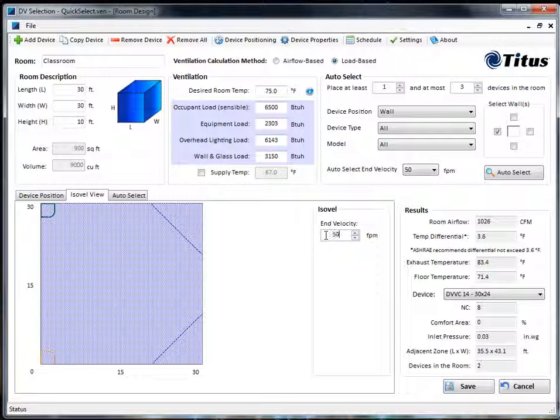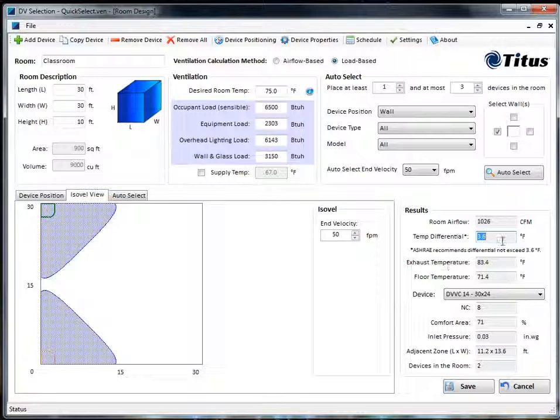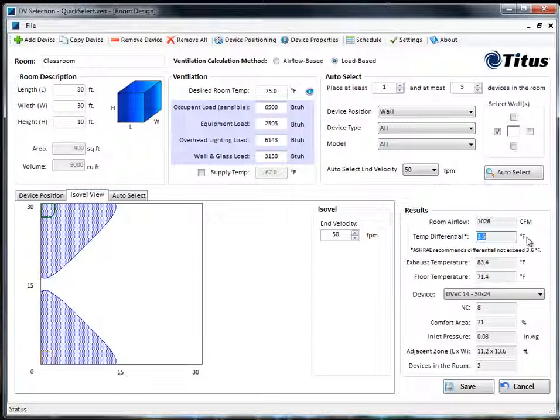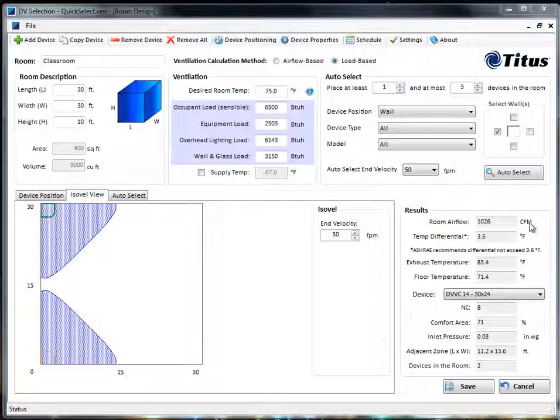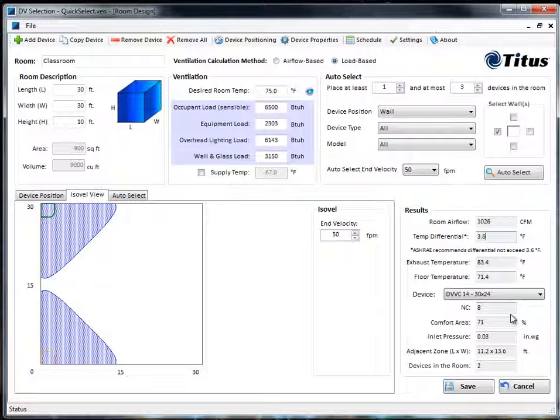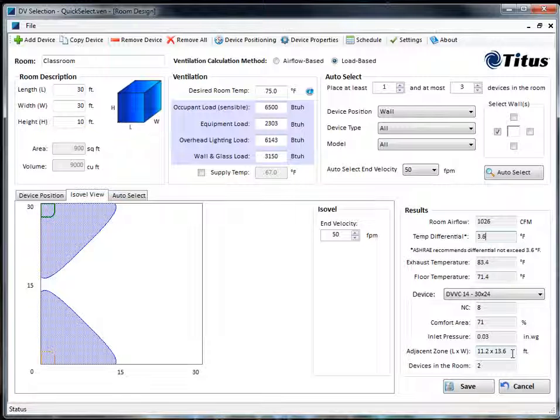Let's take our end velocity back to 50 feet per minute so that the results are calculated based on that number. On the results side you can see your total airflow, the temperature differential of 3.6 degrees. ASHRAE recommends that you don't have a temperature differential from the ankle to the neck region while seated of more than 3.6 degrees, so this is good. You can also see the exhaust temperature, the floor temperature, the model of the unit selected, the NC of the space, the comfort area percentage, the inlet pressure, how big the adjacent zone is, and how many devices you have in the space.